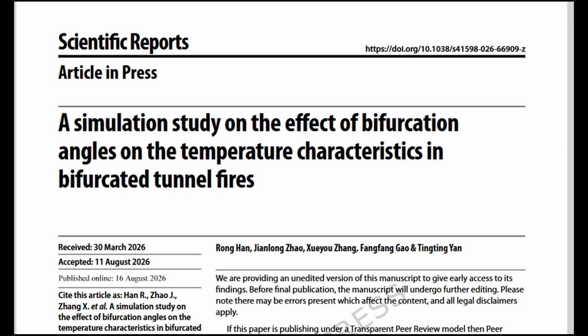For example, the coefficient controlling the slow, lingering decay upstream was a baseline of 0.073 at gentle angles, rising marginally to 0.089 at 90 degrees. This marginal 22% increase means that smoke trying to travel backward into the tunnel entrance cooled off faster when the junction was sharp, because the chaotic flow drew more cold replacement air from the entrance portal.